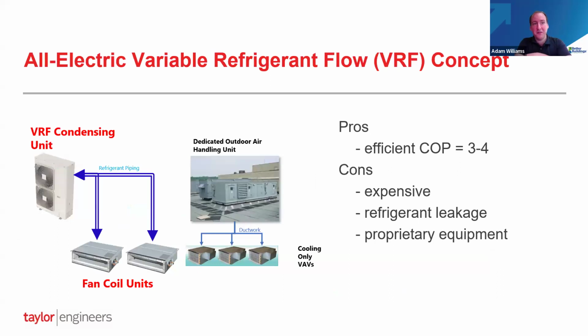Next slide. So the next idea we looked at was a variable refrigerant flow concept. For those who aren't aware of this system, you have a heat pump condensing unit connected with refrigerant pipe to many fan coil units in the space. And then there's a dedicated outside air system that provides ventilation. And on this building, we had a DOAS system that's sized for the full cooling load. So we would have an oversized DOAS system, which could provide 100% outside air free cooling, which does save a lot of energy in a mild California climate to have a full air side economizer. So this system would be efficient. A heat pump system is going to have a COP of 3 to 4. So for every unit of electrical power you get 3 to 4 times the heating output. So it's 3 to 4 times more efficient than electric resistance heat.